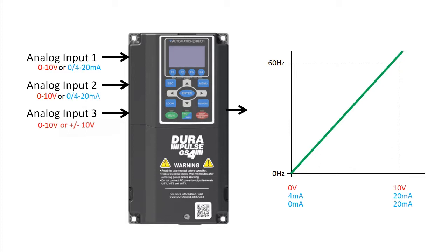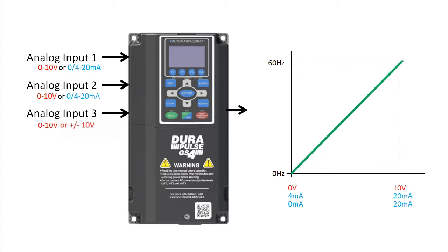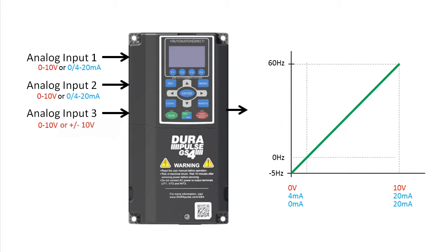You can increase the gain to increase the maximum output frequency. You can add in an offset so the motor has a minimum non-zero speed. You can split the range so half of it drives the motor in a forward direction and half drives it in reverse. You can have most of the analog input range drive the motor in a forward direction but use the rest of the range to jog the motor in reverse.